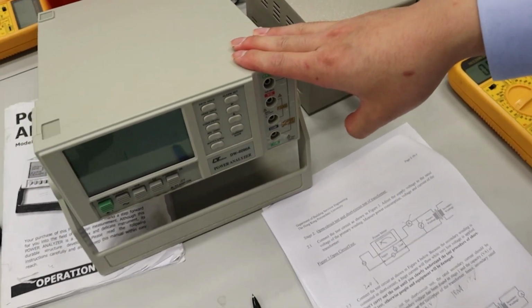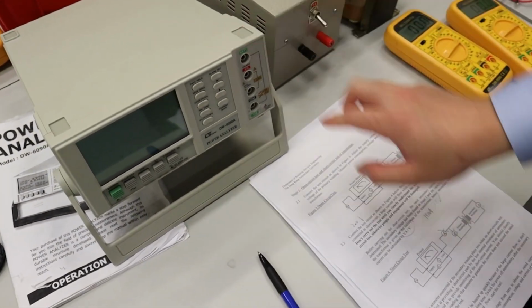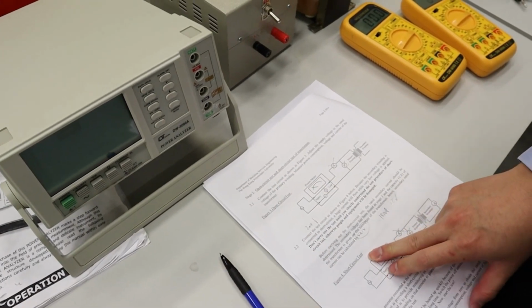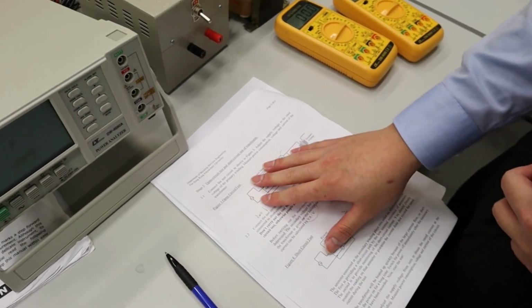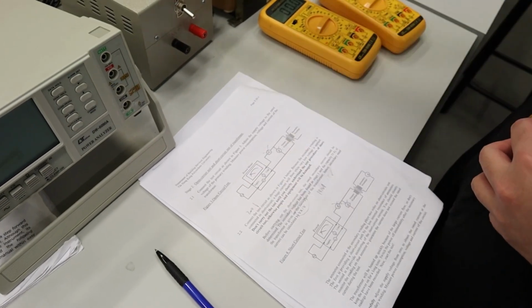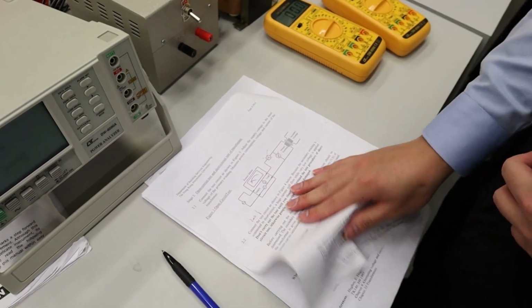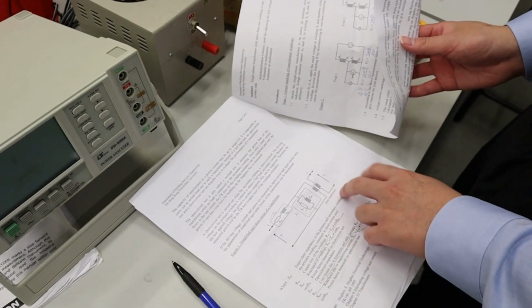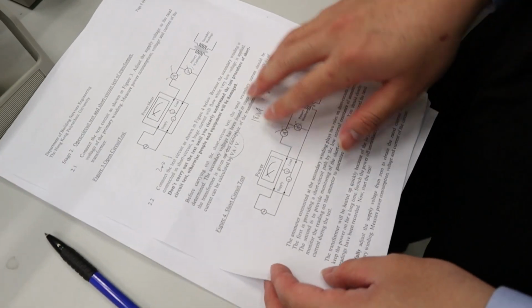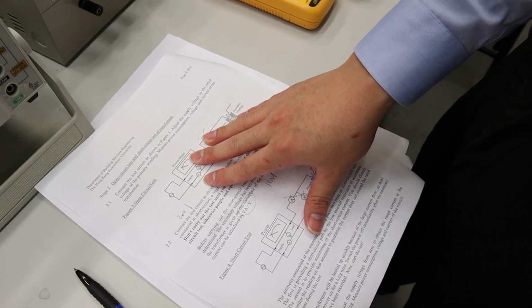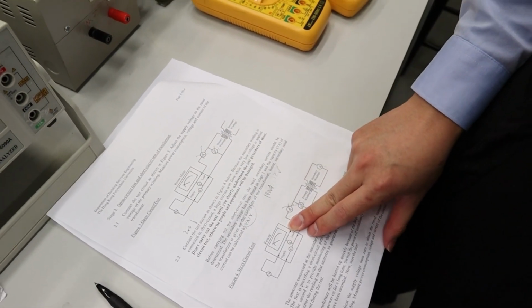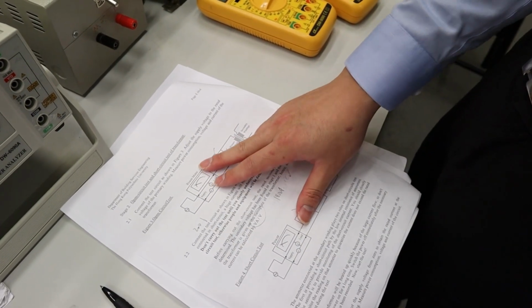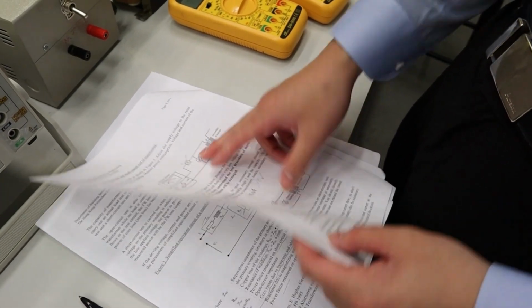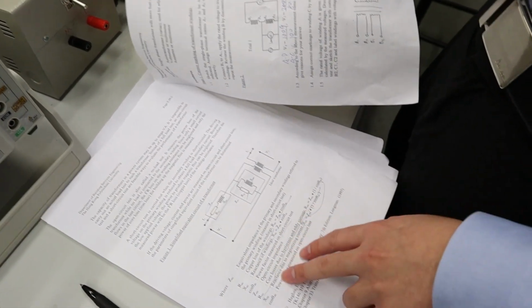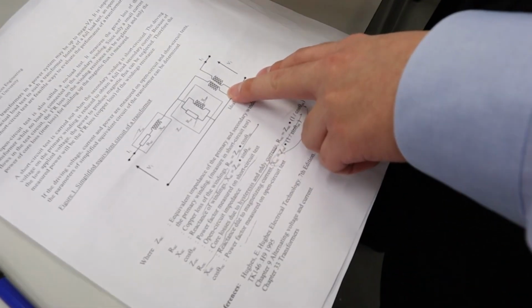The idea of the open circuit test and the short circuit test is to help us understand the structure of the transformers, like the one shown in this picture. After we conduct the open circuit test and the short circuit test, the parameters we measure in these two experiments are going to help us determine the copper loss and the core loss in the transformer.